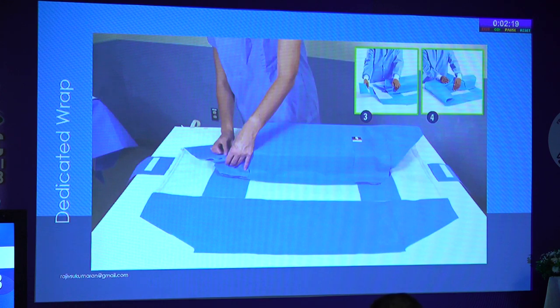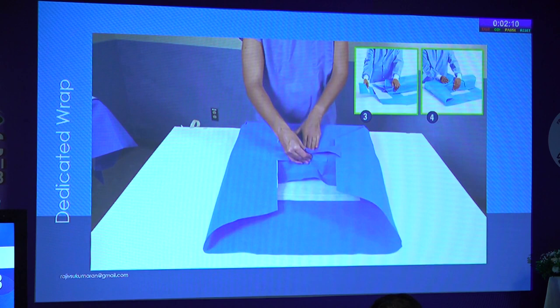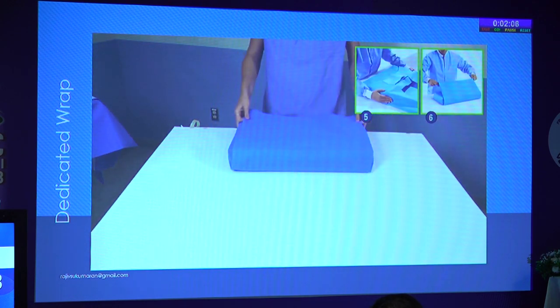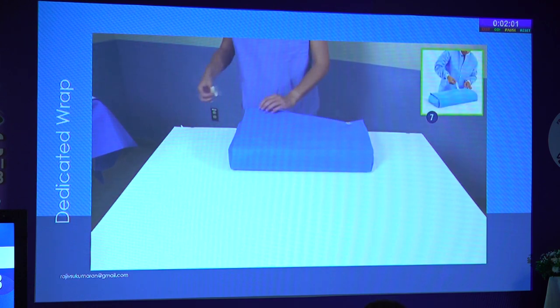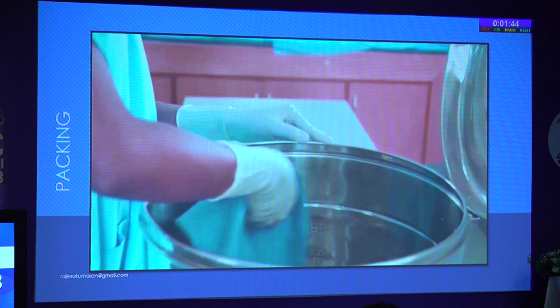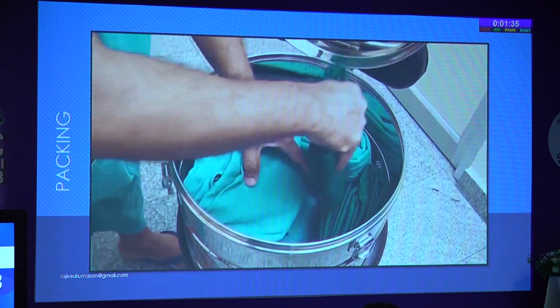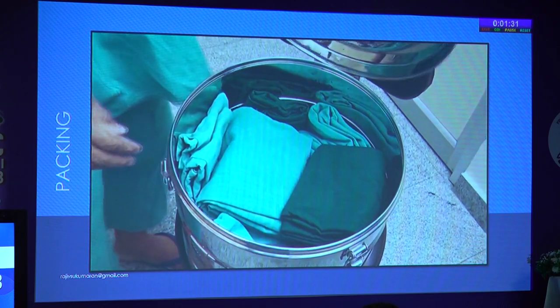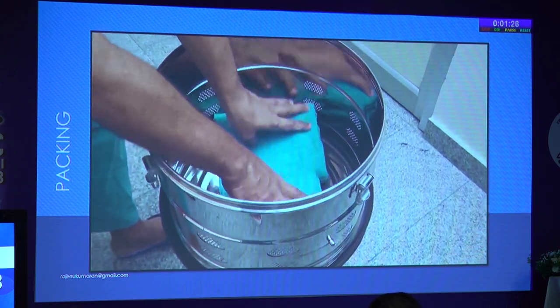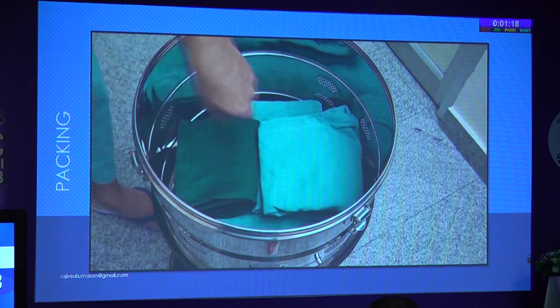The wrapped perforated tray is a reusable material — freely available in Western countries and starting to come into the Indian market. The best approach is one set per case so there is no cross-contamination between two cases. When packing material in a bin — whether linen — you should never pack it tight. Staff tend to load everything without gaps. You must give enough space for the steam and load preferably in one direction so that steam penetration and the process are correct.